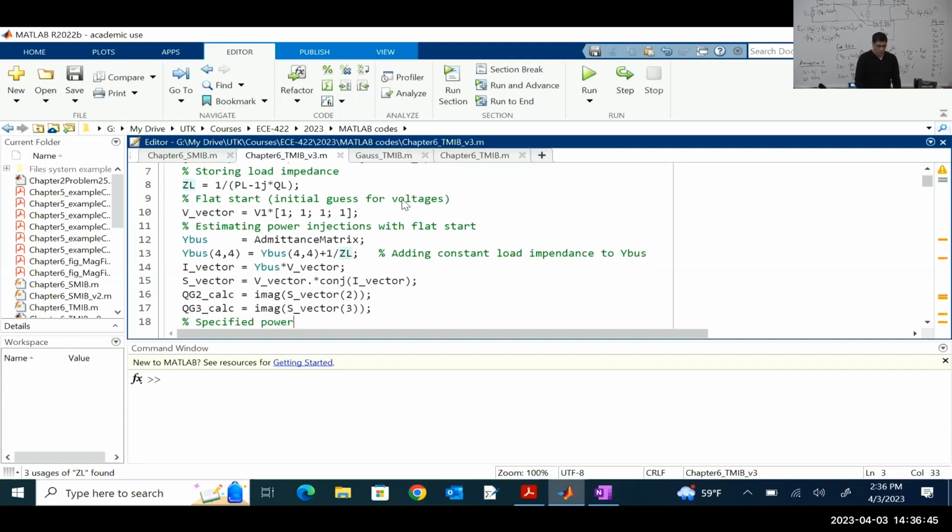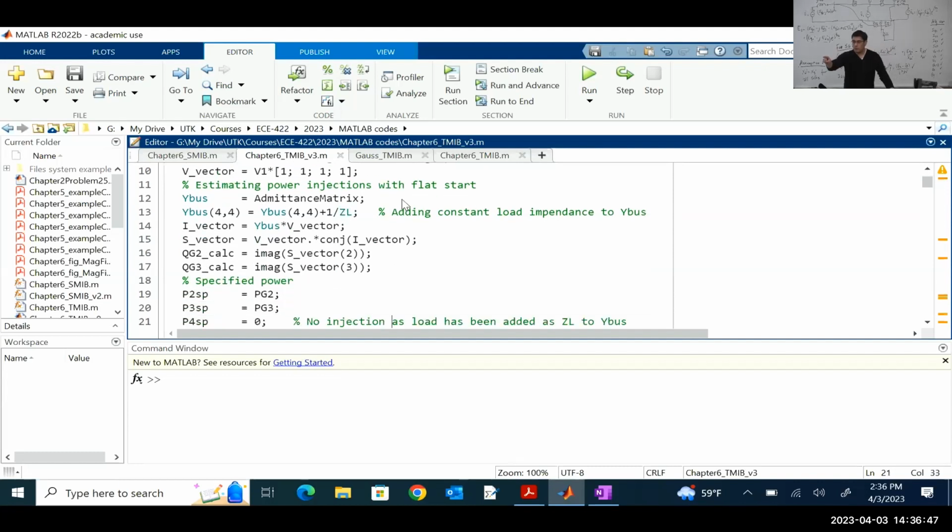What other modification do we have to do? The solution of the power flow, when we solved before the fault, what was the equilibrium point? Because the power flow now needs to be done assuming that the consumption at bus 4 is through a constant impedance, not a constant power load. So that needs to be modified. What is the procedure to modify the equations?